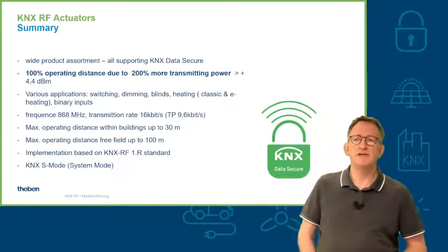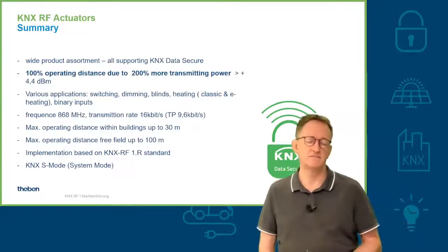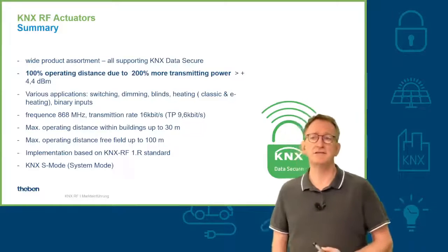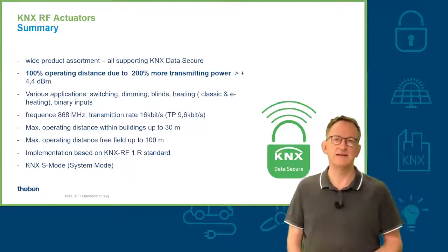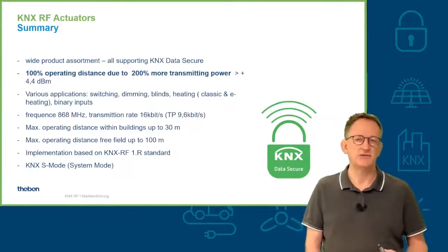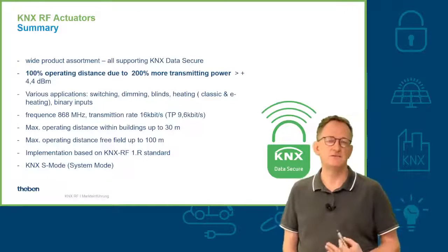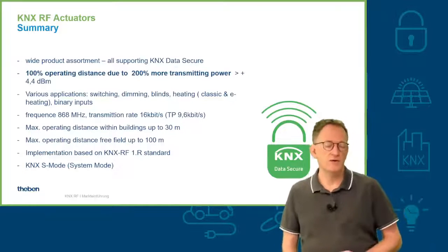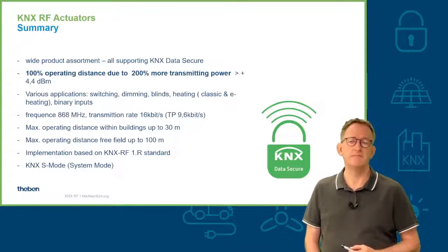A few more information about the configuration of our RF actuators in general. We have a wide assortment of devices, and all of these devices communicate KNX Data Secure. What does it mean? The telegrams are encrypted, they cannot be hacked, they cannot be manipulated. Only certified telegrams will be received and executed. That's very important.